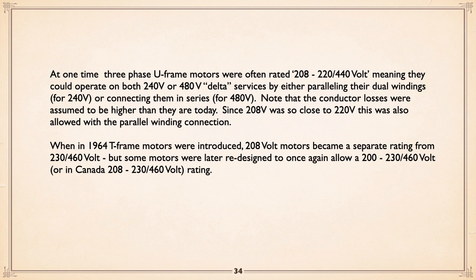But in 1964, when T-frame motors came out, the gap was too big. They upgraded the motor voltages and the gap was considered too big, so 208 or 200 became a separate voltage rating from 230, 460. But some motor manufacturers, Toshiba being the first that I'm aware of, were designed to again allow a 200, 230, 460 rating, or 208, 230, 460 in Canada. They simply up-designed the motor slightly. Then you could use that motor with the three voltage ratings on any of the three voltages. You didn't have to have two separate motors in stock.